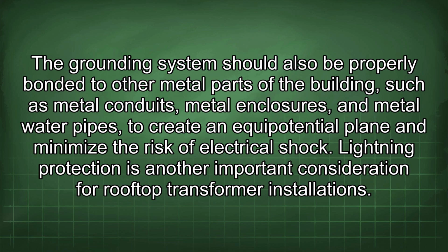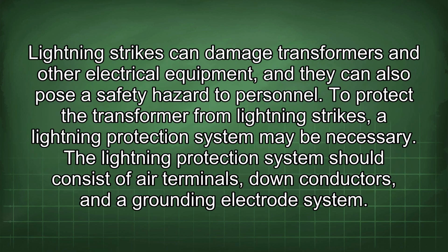Lightning protection is another important consideration for rooftop transformer installations. Lightning strikes can damage transformers and other electrical equipment, and they can also pose a safety hazard to personnel. To protect the transformer from lightning strikes, a lightning protection system may be necessary. The lightning protection system should consist of air terminals, down conductors, and a grounding electrode system.